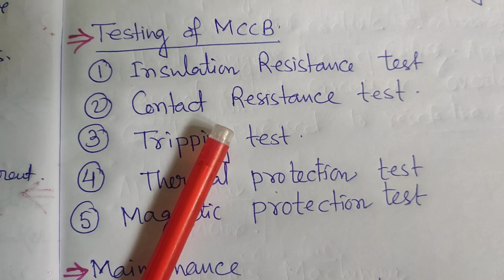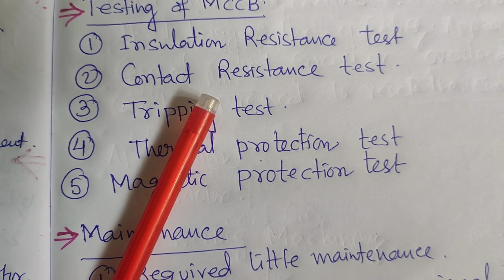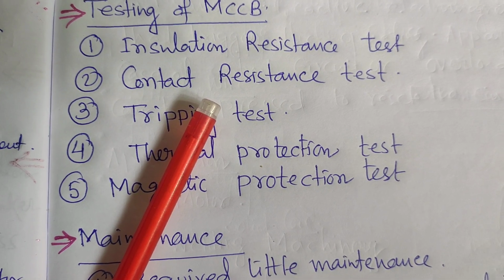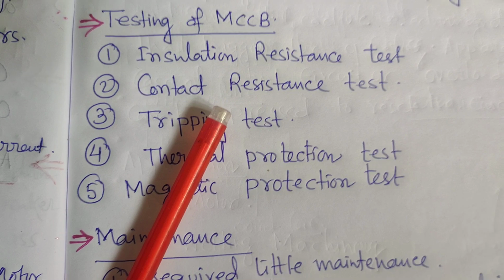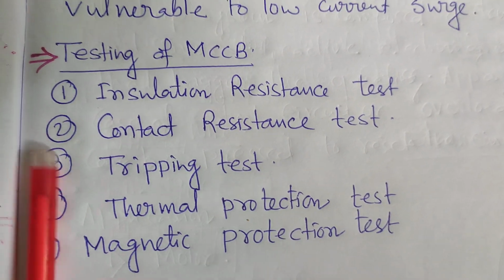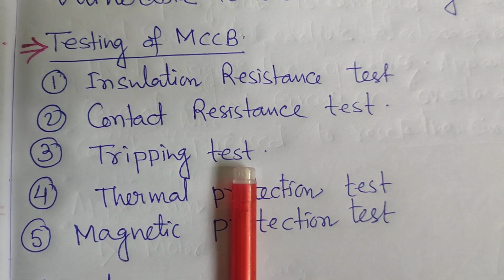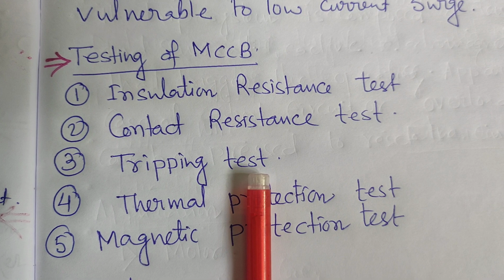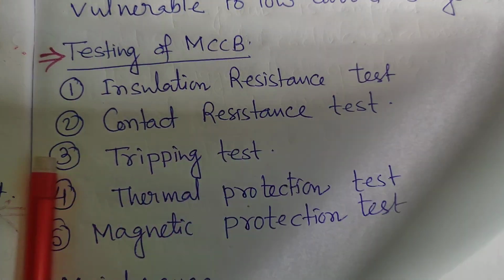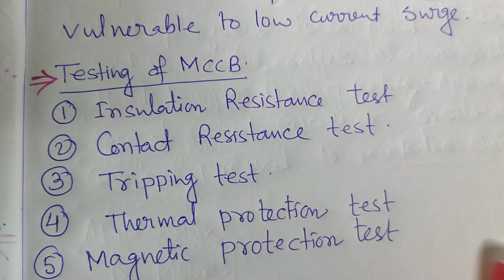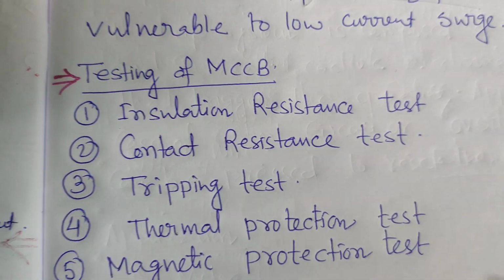Now we discuss the testing of the MCCB, the different types of testing we have to do during winter maintenance and pre-puja maintenance. We have to check that the MCCB is in good condition, or whether some deterioration is starting. So we do an insulation resistance test of the MCCB. Contact resistance test: we have to check the contact resistance. What is the contact resistance? If the contact resistance deteriorates, the current will change. Depending on the resistance, the current will change. If the resistance is high, the current will be low. If the resistance is low, the current will be high. So we have to check the contact resistance.